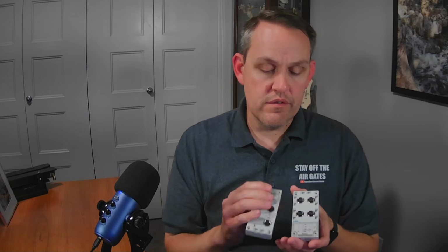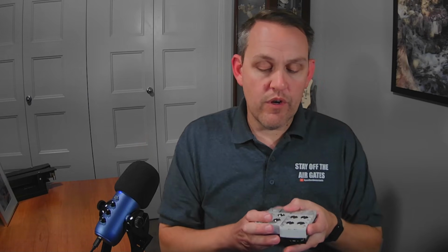Different types of processors are out there. This is a remote processor that can be used somewhere. Basically, this fits into another rack or a smaller rack, something just like this, and then it's a modular system, so we can put the processor in on one side, and then, I'm sorry, they're upside down, and then keep adding more I/O expansion cards and just keep building them bigger and bigger. Now, one of the ways these connect and we can see them is that we have a computer in the PLC room that is linked with the controller so we can see it.